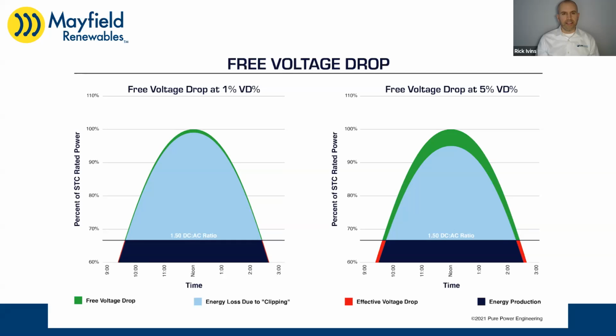So it sounds like you basically have to run through the calculation. There are two equations: first you calculate what the voltage drop would be at STC, and then you take that and put it into PVsyst and run it. You can run a few different iterations, calculating conductor size and voltage drops, and then put that into PVsyst to figure out the energy gain or loss from the different design parameters.